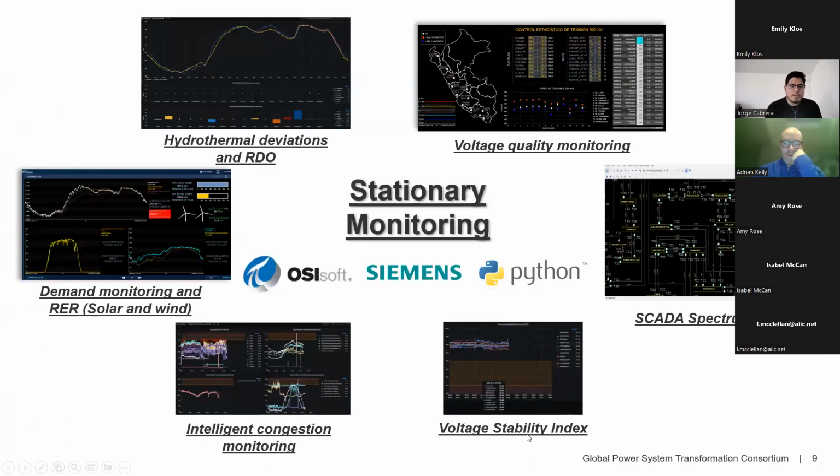For example, regarding the stationary monitoring, we use the OSIsoft PI Vision system. We have some applications based on Siemens, and others based on Python with a specific mathematical model. We have the hydrothermal deviation for redispatch, voltage quality monitoring, SCADA Spectrum Power 7 for monitoring the whole power system, and a voltage stability index for load bus bars. We also have an intelligent congestion monitoring that analyzes the whole grid around the country every 5 minutes.